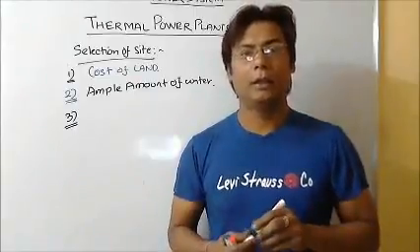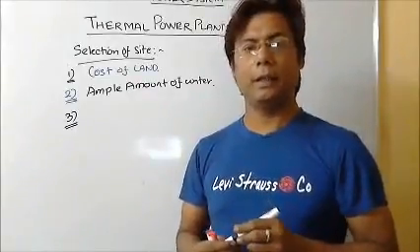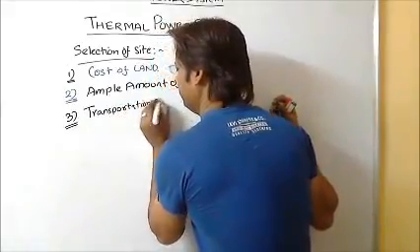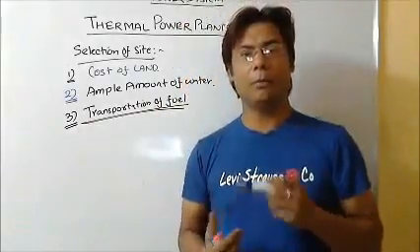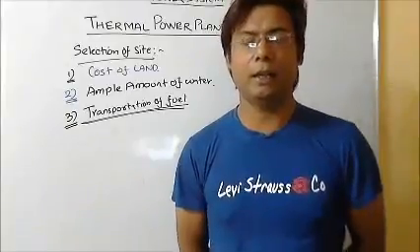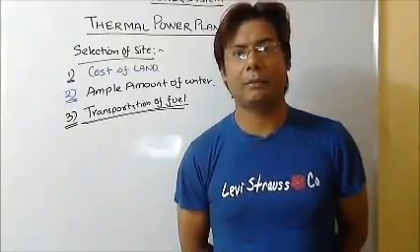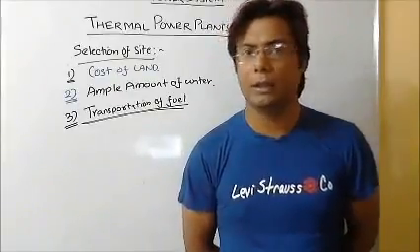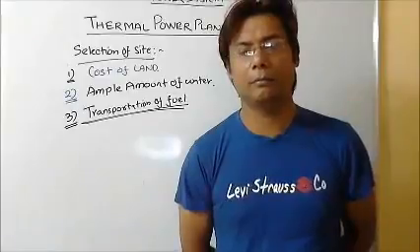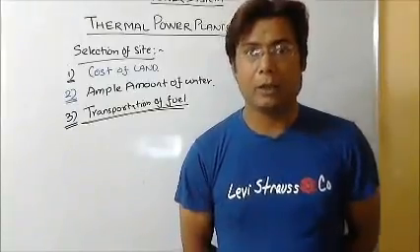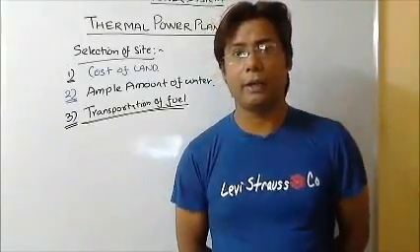The first thing which is very important in selection of the site of a thermal power plant is the transportation of the fuel. Transportation of the fuel is the most important point under the selection of the site, because the cost of the land will be a one-time investment. If the water is available there, then there is no issue. But the running cost of the whole power plant and the efficiency of the power plant solely depend upon the transportation of the fuel as well as the fuel quality.